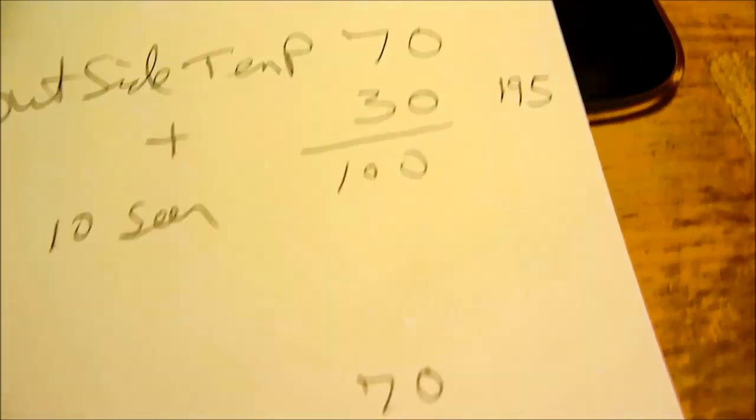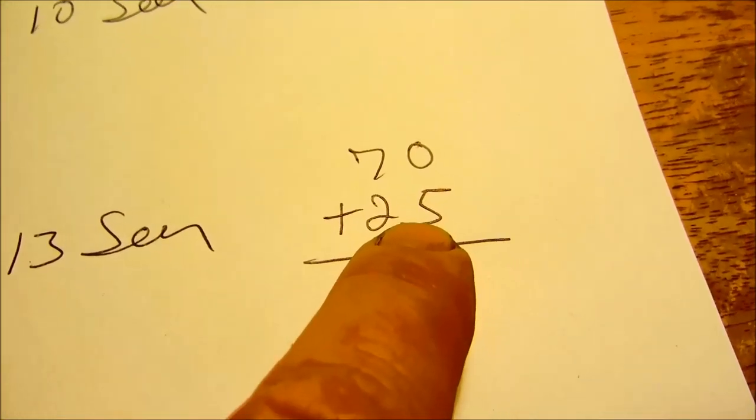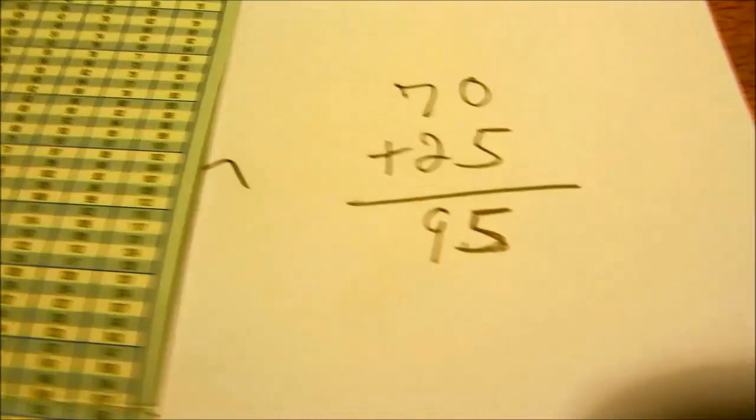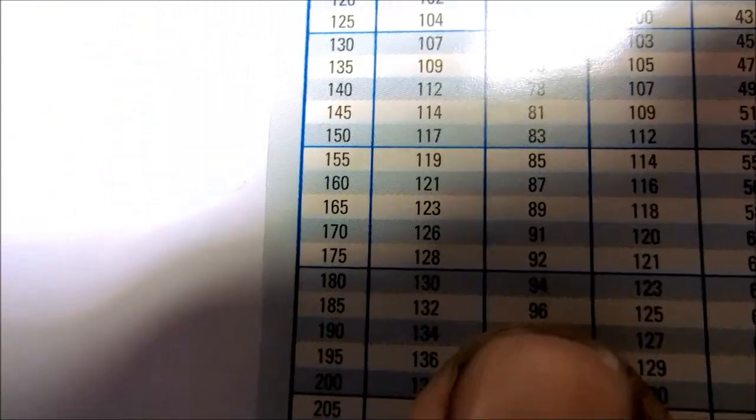On a 13 SEER you drop down to 25. The higher the SEER, the lower the number. So 70 plus 25 is 95. On the R-22 scale you go to 95, we'll say 94.